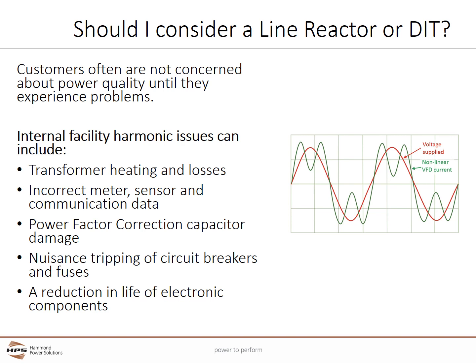Internal facility harmonic issues can include transformer heating and losses, which can reduce the life of a transformer, and incorrect meter, sensor, and communication data. Power factor correction capacitors can be damaged and fail. There can be nuisance tripping of circuit breakers and fuses caused by the addition of harmonic currents. And finally, a reduction in the life of electronic components, usually such things as DC power supplies, which will often keep failing.